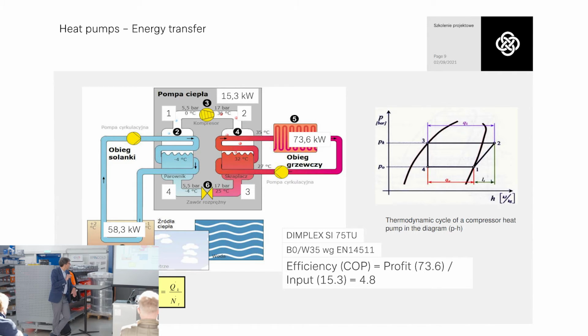So this circuit is closing all the time, running the same way. This process is described by the COP factor. What is this? This is the coefficient of performance, and this factor gives us information about the efficiency, how much profit we get from this process compared to the input. So, for example, if we get 73.6 kilowatt output power, we need to use 15 kilowatt of electrical energy for running the compressor. It gives a 4.8 COP factor.